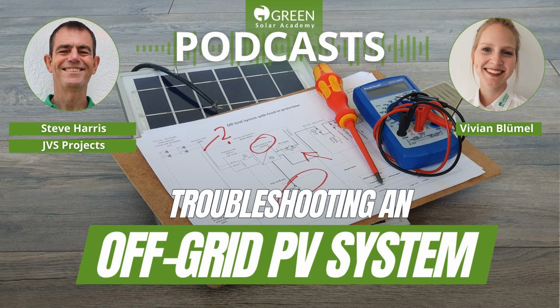Moving on from that, the whole sequence of connecting and starting your inverter, connecting it into the batteries, the charge controllers, all the rest of it is laid out usually in the manuals of the inverter and the equipment. And I mentioned this thing about taking 5 minutes or so to think about a design earlier on. The number of people, and I don't know what it is, it might be a guy thing. I've never understood it, because I'm a guy and I read the manual. Read the manual, because it's simple. Those manuals were written for a reason. Read the manual, guys. You'll save yourself a world of pain. Just read it, and it'll give you the sequence on how to switch on.